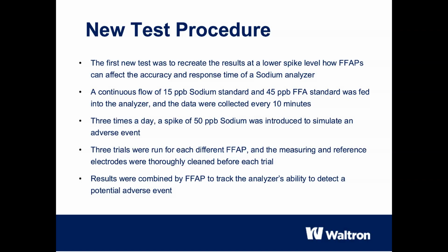For our new series of tests, we wanted to replicate the conditions and observe the effects more closely. The main goal was to see if we could replicate the previous results, albeit at lower sodium and FFA levels. We introduced a continuous flow of 15 ppb sodium and 45 ppb FFA standard into the analyzer and collected data every 10 minutes to observe slow drift effects. To simulate an incident, such as a condenser leak, we applied a spike of 50 ppb sodium 3 times a day. We conducted 3 series of tests for both FFAPs and, very importantly, thoroughly cleaned the measuring and reference electrodes before each test to ensure a clear baseline.